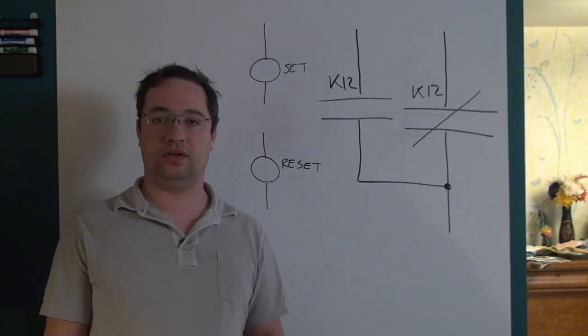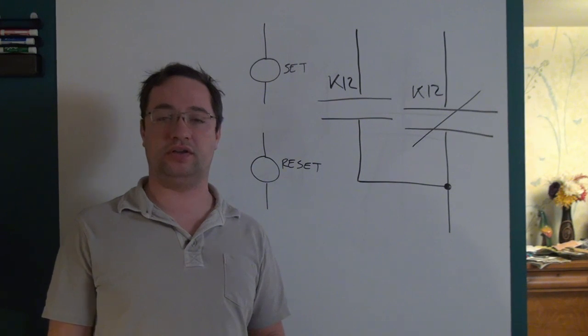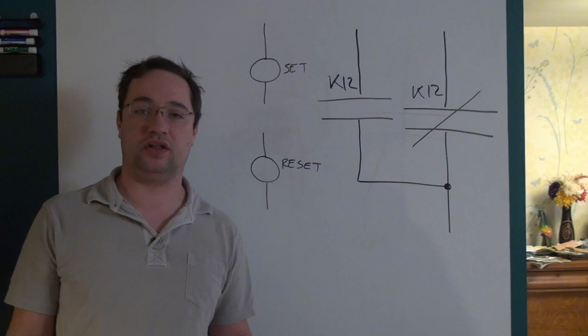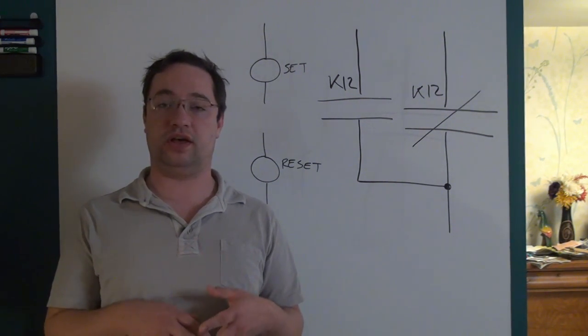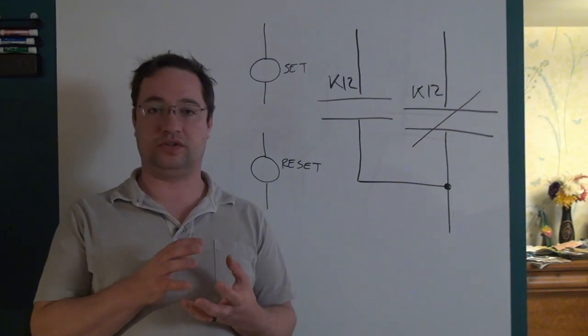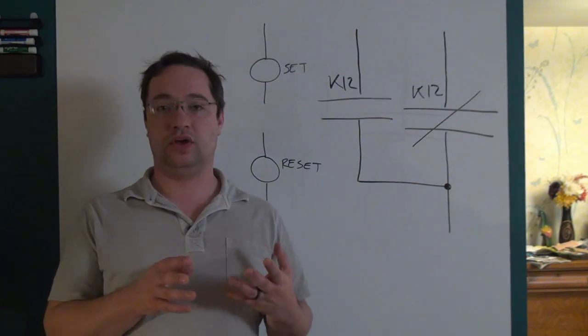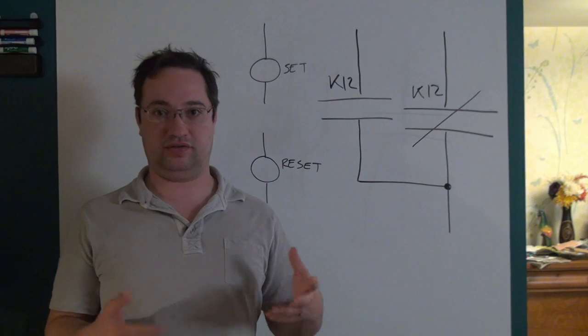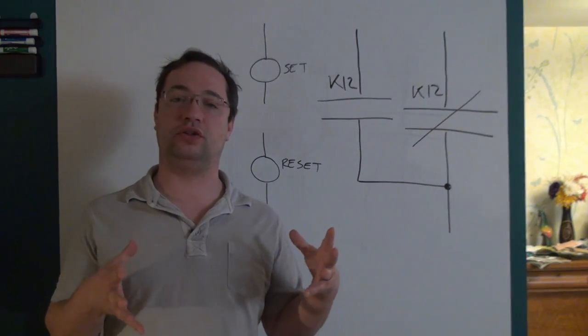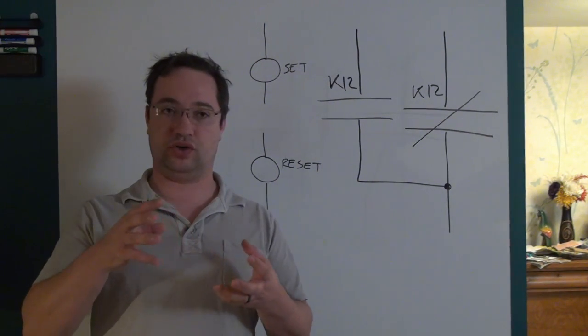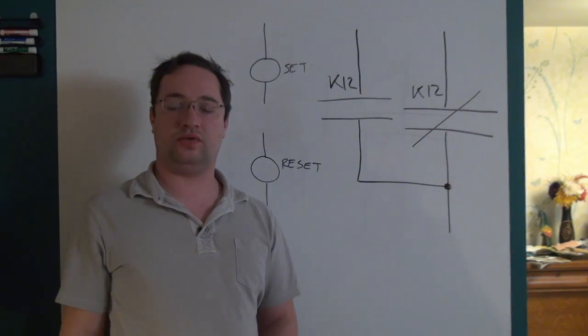The final relay variant is a safety relay. Safety relays are designed so that the spring inside is specifically large enough that if the contacts were to weld themselves closed, the spring is strong enough to rip them apart. Because it's called a safety relay, it's obvious that it's used on safety circuits — particularly e-stops. These relays tend to be very large because the coil needs to be large enough to move a spring of that size.